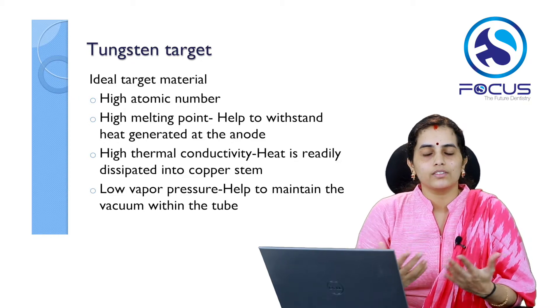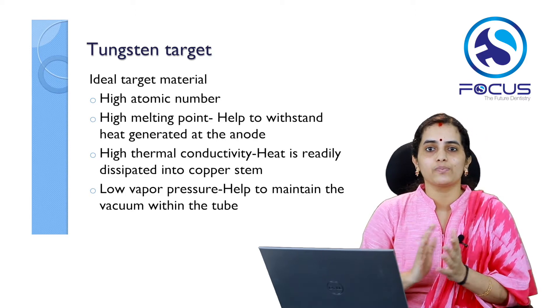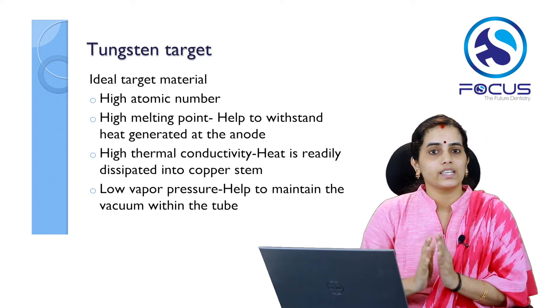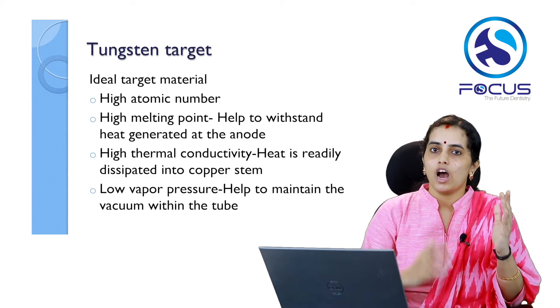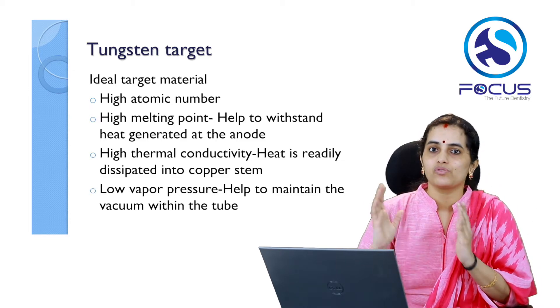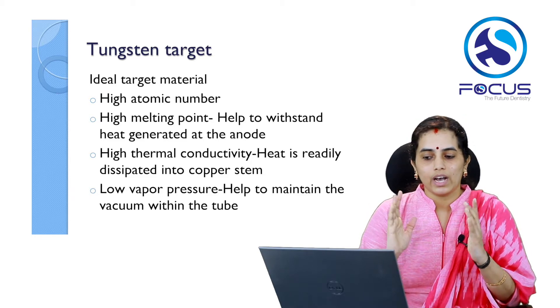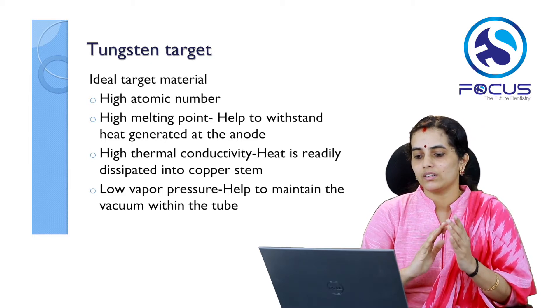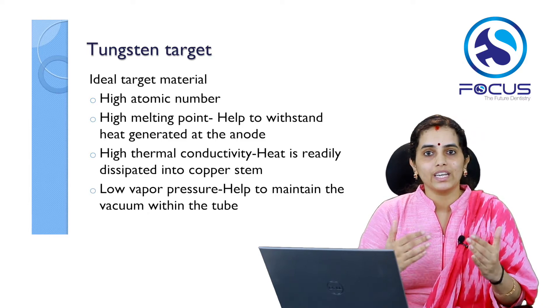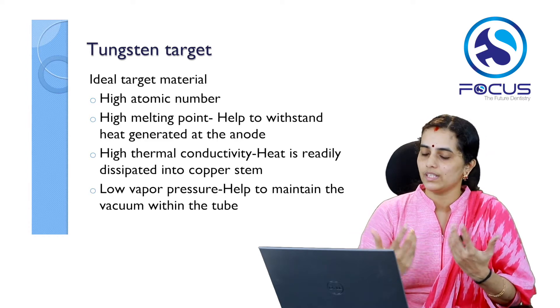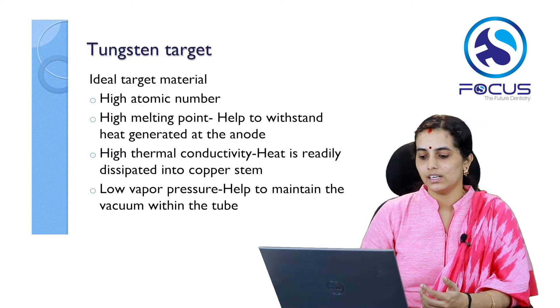Tungsten is considered the ideal target material for several reasons. It has a very high atomic number, so the X-rays produced are of very high quality. It has a very high melting point, helping it withstand the heat generated at the anode, since 99% of the electron beam striking the target is converted into heat. It also has high thermal conductivity, readily dissipating heat onto the copper stem, and a low vapor pressure, which helps maintain the vacuum within the tube.